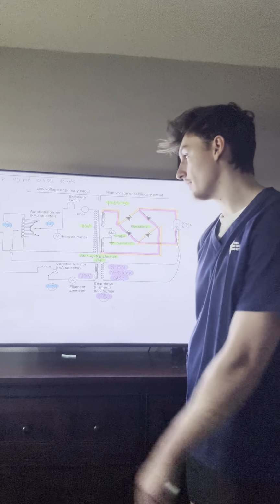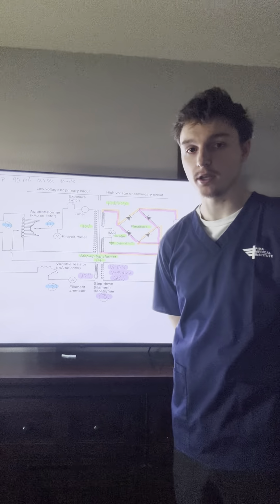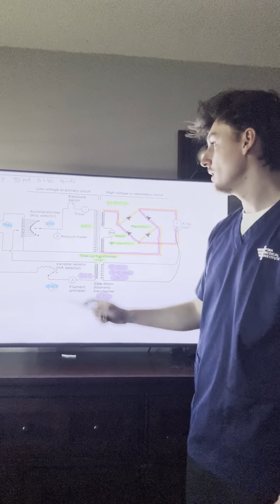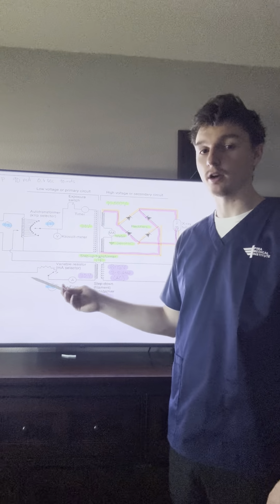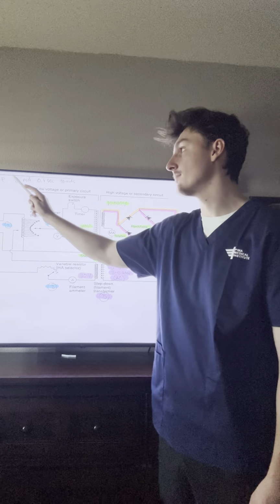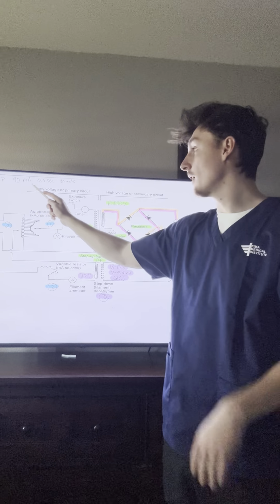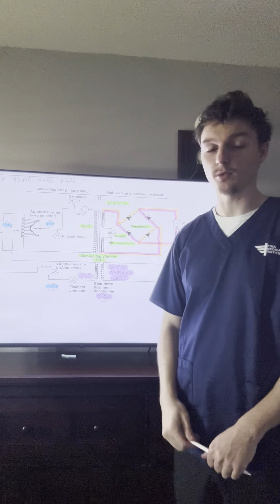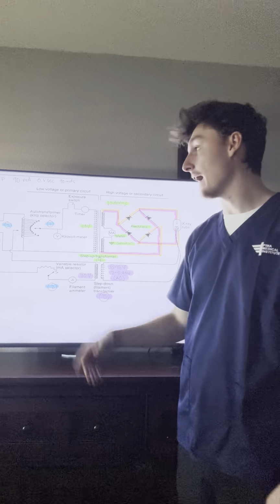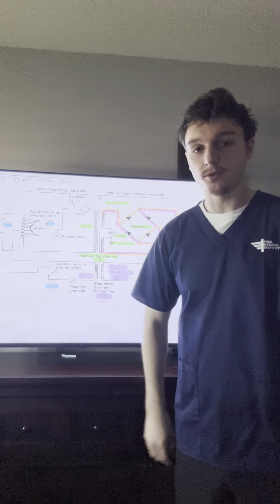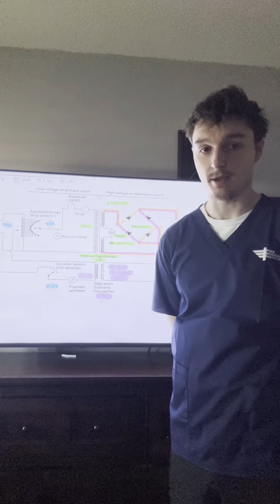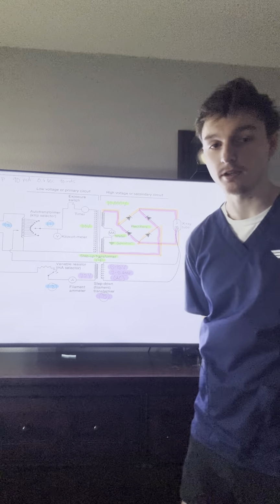And before we talk about all of our points of induction right here, we're going to talk about our technique. Our technique is going to be 70 kVp at 90 milliampere at 0.1 seconds, and what that will transpire to is 9 mAs. So 70 kVp at 9 mAs is what our technique is going to be for this.